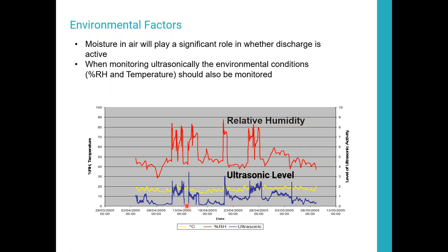And what they found here was, this was switchgear. They had a basement, a room underneath that had moisture problems. They had dehumidifiers in there, and the dehumidifier failed underneath this section of gear. So in reality, they had low levels of PD, but they did have some PD. When the humidity went up in the room below it, it came up in the gear, and it caused PD to intensify. Over a period of time, this PD level probably would have increased to the point where it would have been steadily higher. But the humidity actually showed them that they had a problem. If I remember, it was two non-shielded cables close together. So they were able to separate the cables, pull them apart. That took away the PD source. And then they went and investigated the humidity problem. But that's just tying together your humidity versus your surface discharge activity.